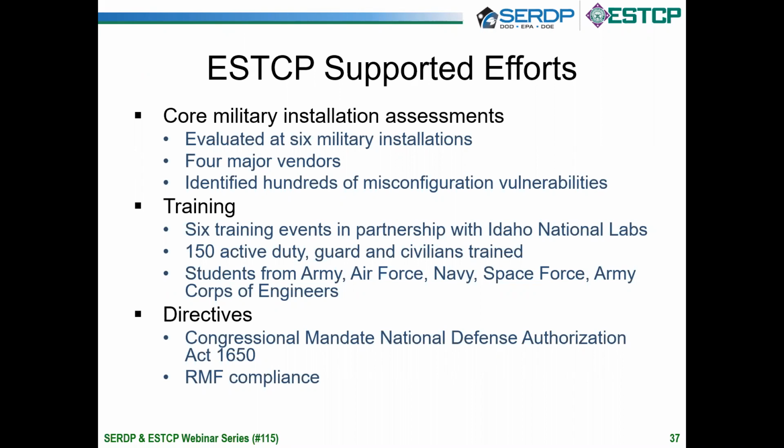And so through the ESTCP report, we were able to evaluate 6 different military installations. We had 4 different major vendors. That's Tridium Niagara, ALC, Siemens Apogee, and also Johnson Controls Metasys. And so through the assessment teams on 1650, we've identified literally hundreds of misconfiguration vulnerabilities. We're also able to provide some training to the various assessment team members, and this gave us some really good data as far as the efficiencies that BASIC is realizing.